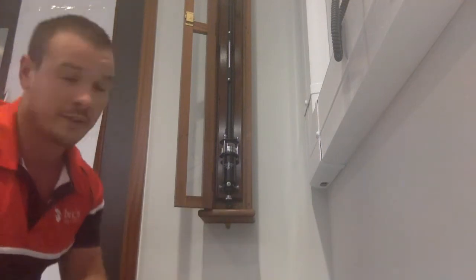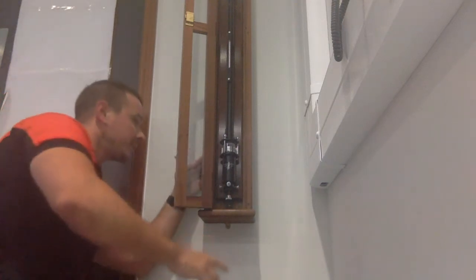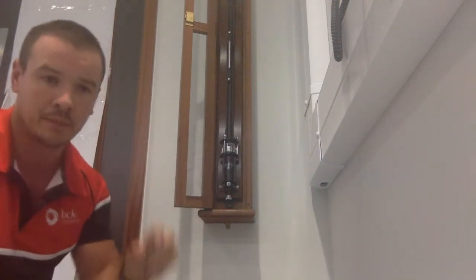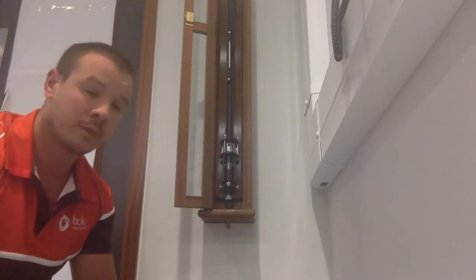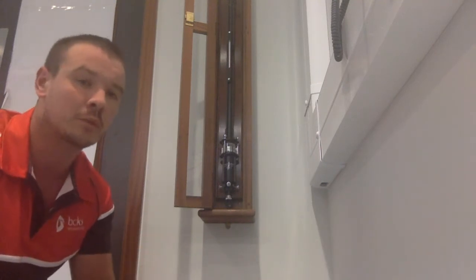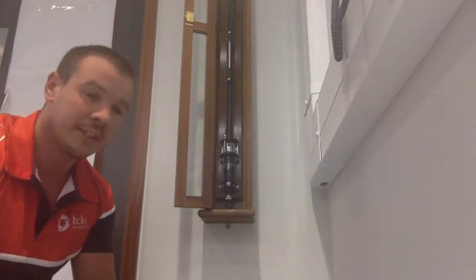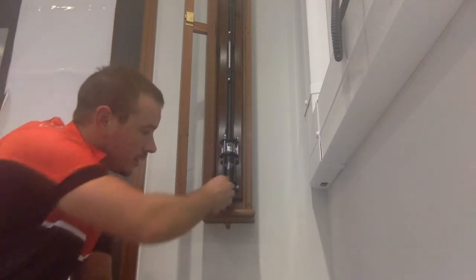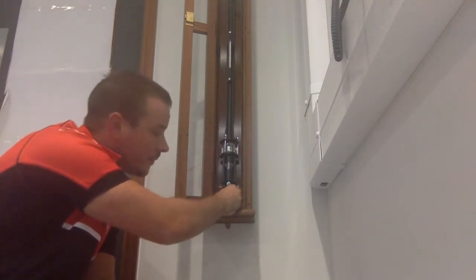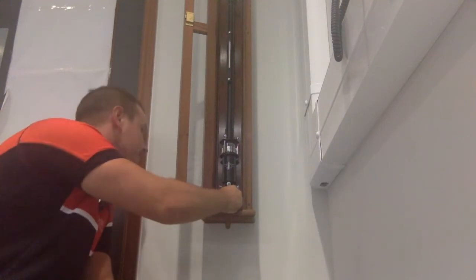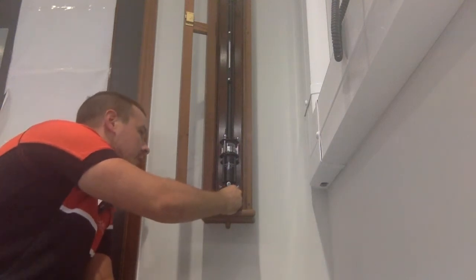At the bottom of the barometer is a small reservoir of mercury. And at the back of that river, if you look from the side, you'll see a small plastic point. What you want to make sure is that the mercury is just about touching that point. If you need to move it up or down, you can use this screw at the bottom and just either loosen or tighten until the pin is just about touching the mercury.